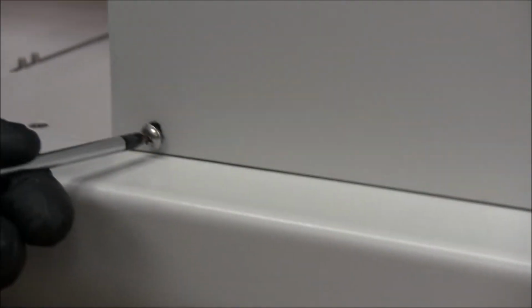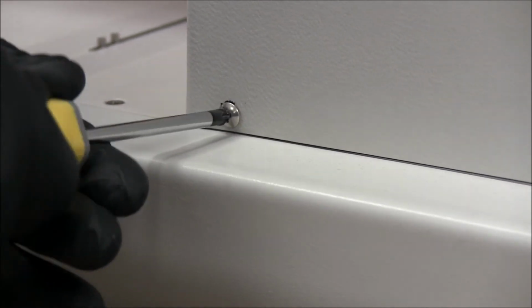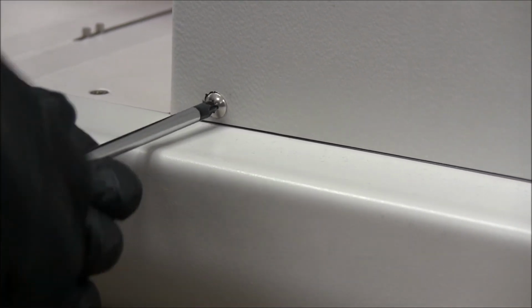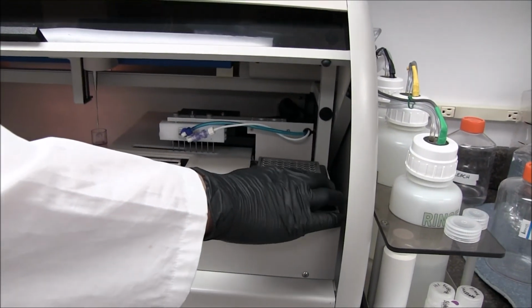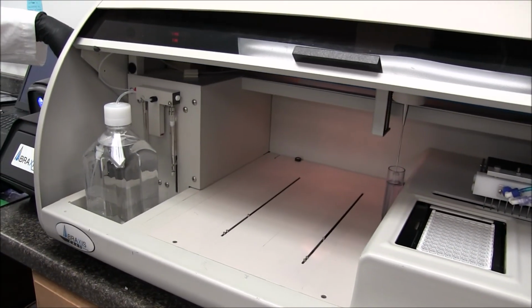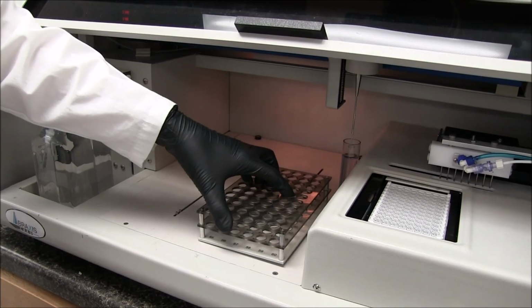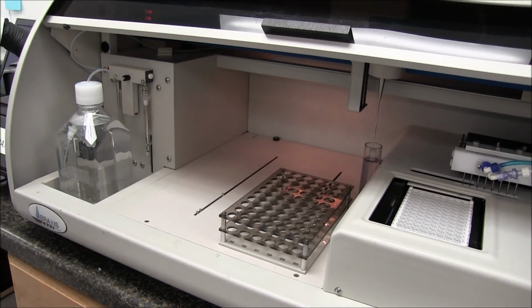Sometimes the plastic covering must be slightly shifted or bumped in order for the screws to grasp their threading. If done correctly, only minimal effort should be required to fasten these screws. The alignments have now been made. Replace the reagent and sample racks, then continue with normal assay procedures.